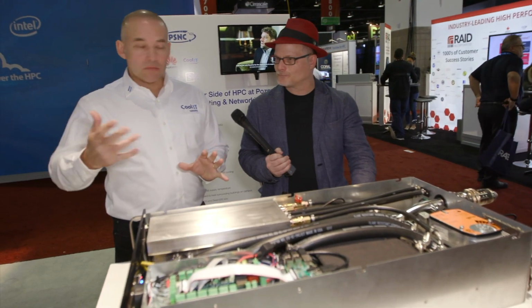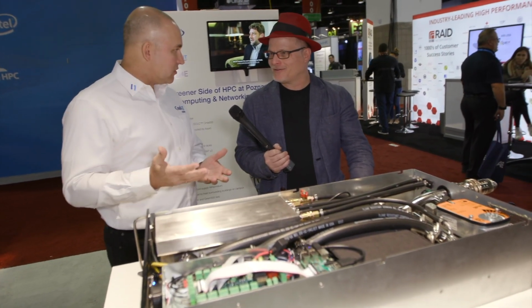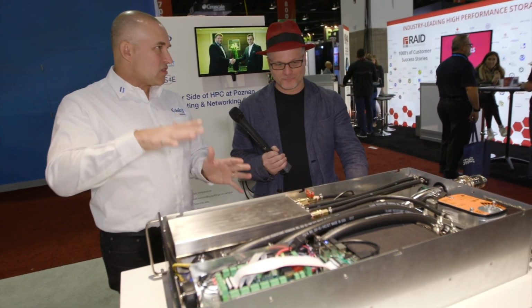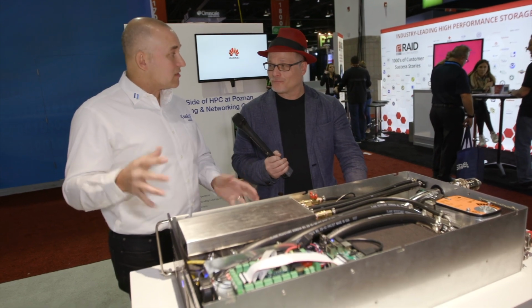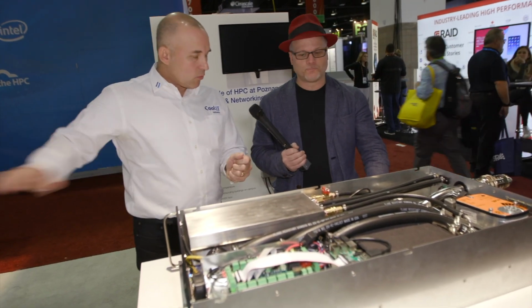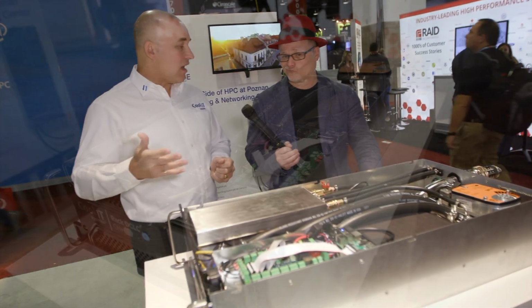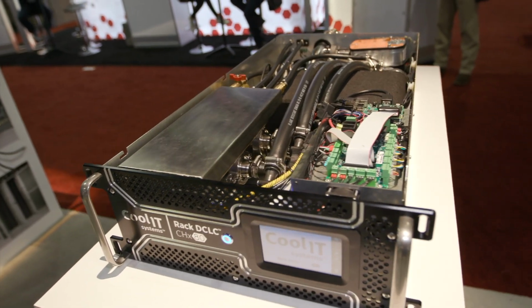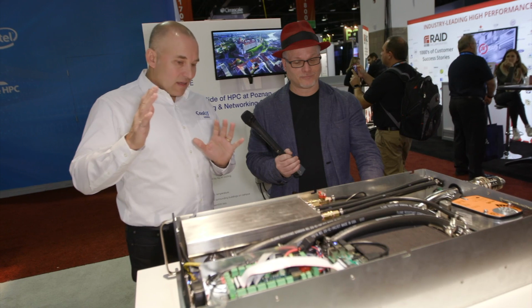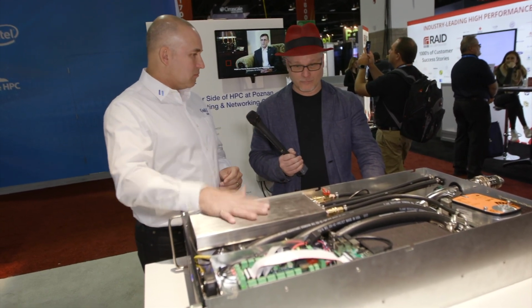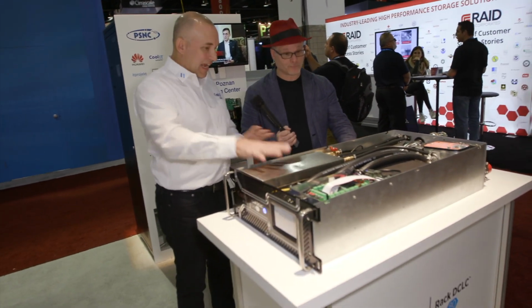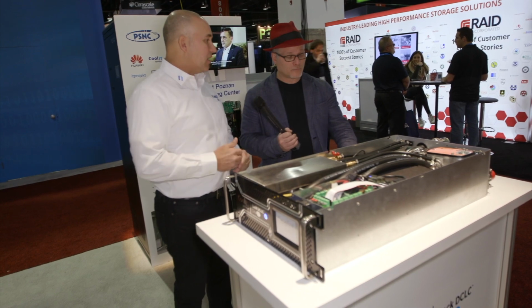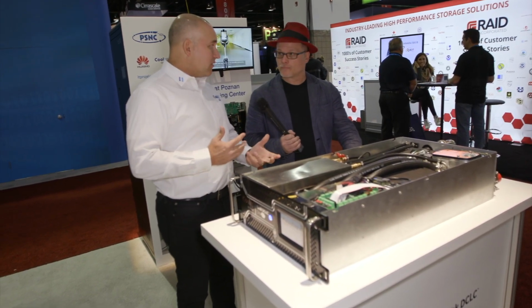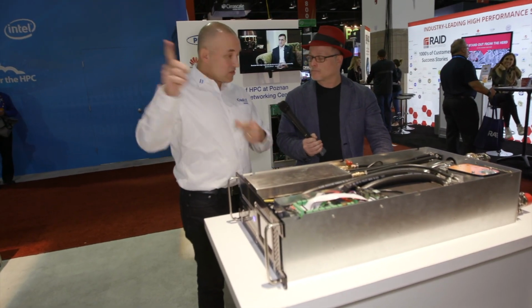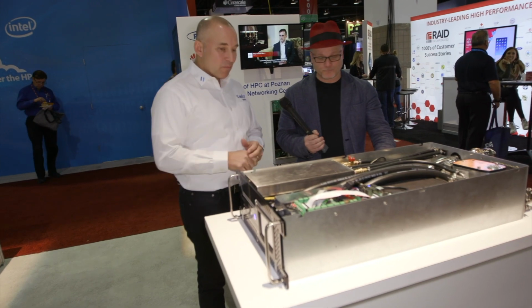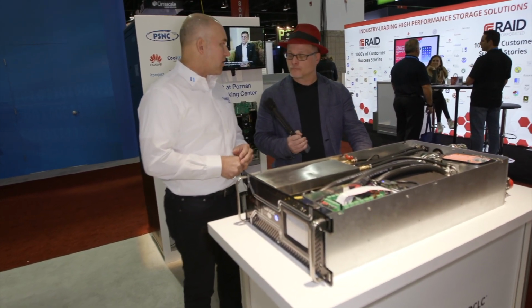So in almost all of our configurations, we call it a hybrid direct contact liquid cooling. So we take 60, 70, maybe 80, or even as high as 85% of the heat inside the server and absorb it into the liquid and then whisk it away that way. That still remains a fairly high percentage of heat, and especially in these very dense configurations that needs air cooling. So let's say we grab 80%, this would be in a position to cool a 100 kilowatt rack, taking 80% in water at 80 kilowatts, leaving 20 kilowatts to be air cooled. That makes a nice dovetail for our partners with STULZ, and we'll see a combined product that we did in a little bit, but it has turned into a great value proposition for our customers.